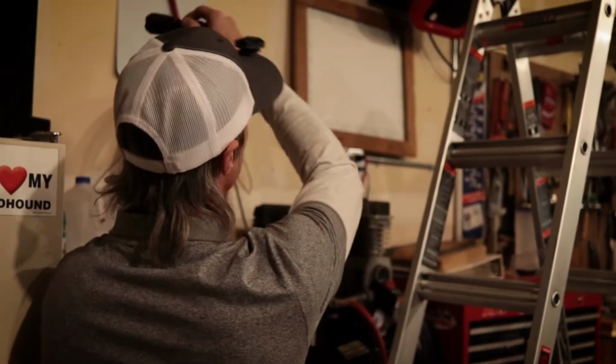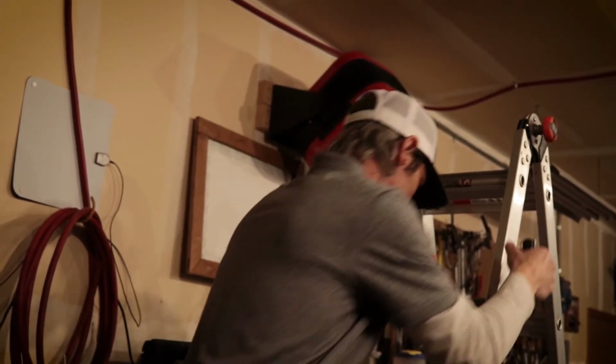Absolutely, a direct connection. This is the master bedroom, so you can see the effect of how the design of the home currently is and how it's causing the walls to perform. Based on our thermal readings, I should be able to get up here and see that, one, we know cold air is coming in from the outside and dumping over into the bedroom, but two, a lot of those walls need to be sealed up because the cold air from the attic is getting right into the walls, which is cooling off their bedroom, their bathroom, and everything.